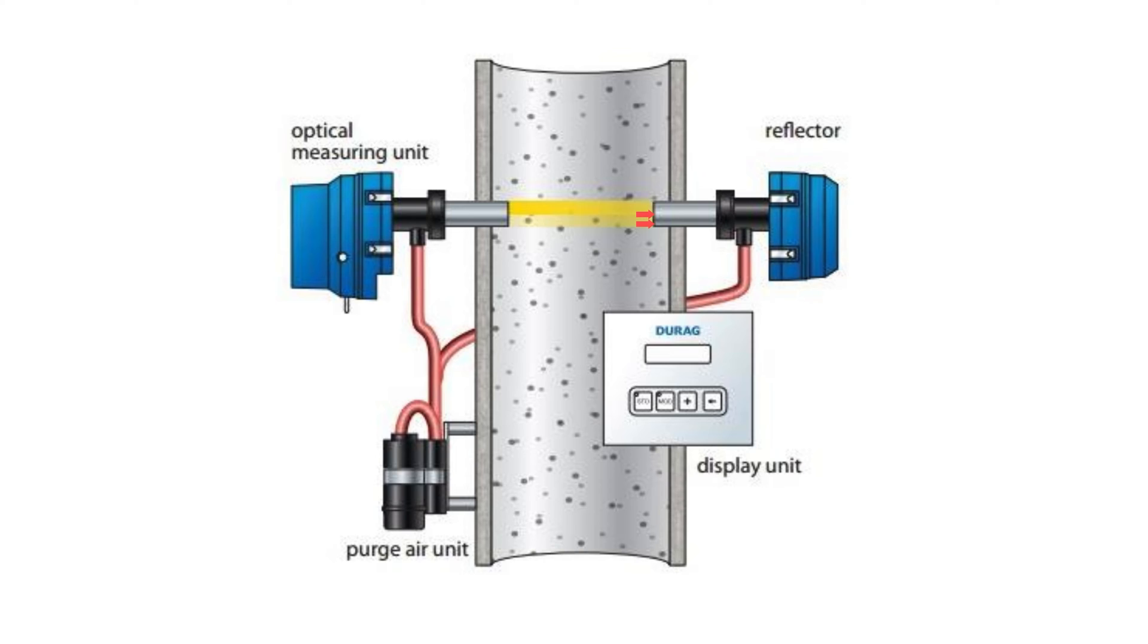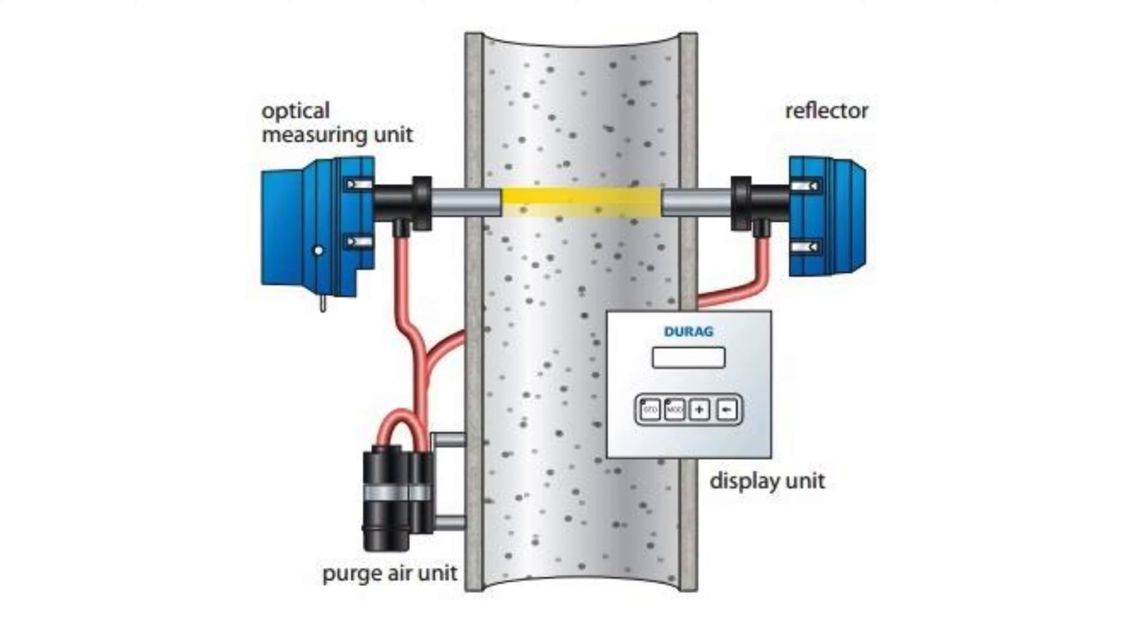Dust and opacity monitors operate on the basis of the transmission principle. The measuring head sender and the reflector receiver are fitted opposite to each other. The transceiver emits a beam of light which passes through the stack or duct and strikes a reflector. The light beam is reflected back and the amount of light returned is measured by the transceiver.